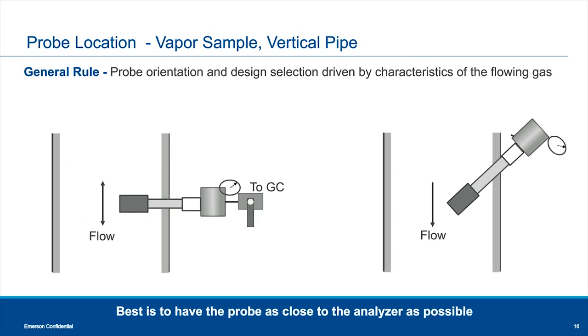If your pipe is vertical, you have two options: probe positioned horizontal or at a 45-degree angle. The probe tip type matters more in a vertical pipe — whether it's square or slanted. For a squared probe, it's only recommended for downward flow. For upward flow, you'd want a slanted or cut probe surface to help avoid contamination. Understanding your composition, flow rate, and flow direction becomes more critical with a vertical pipe.